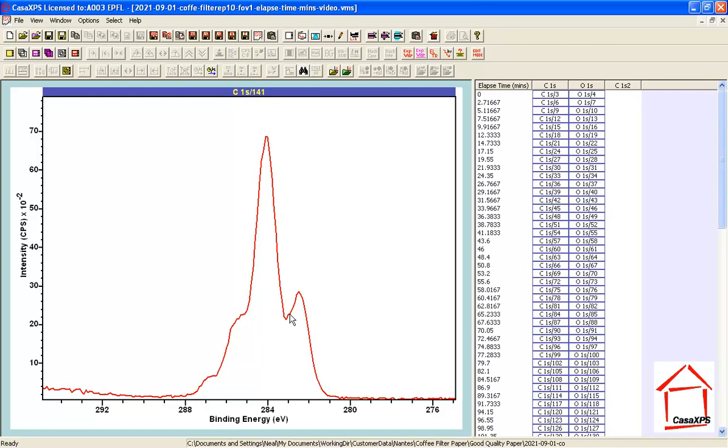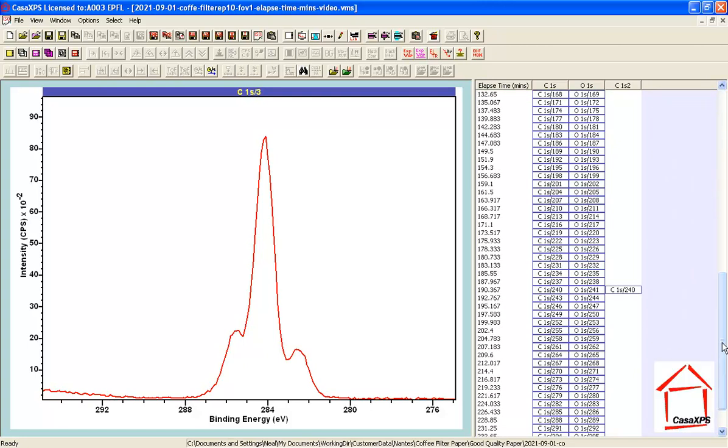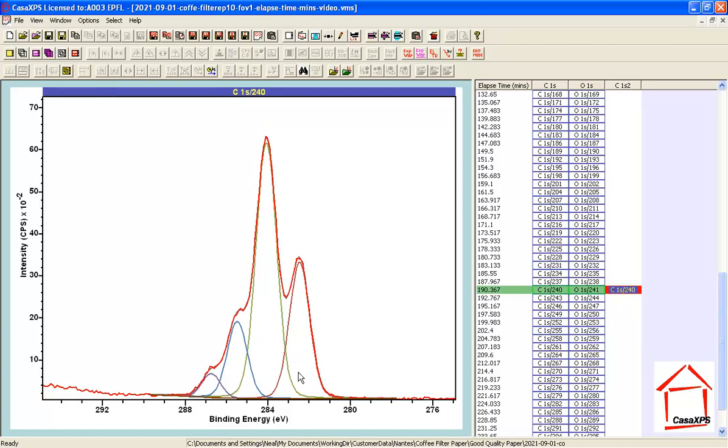Then what we would like to do is be able to fit a spectrum such as this with components that are consistent with other fits throughout the entire data set. So let me illustrate what I mean by an inconsistent peak fit. Here is a peak model. Now, you can argue over whether there are four, five, or more peaks in this peak model, but at least in this instance, four component peaks fit these data, and throughout the entire data set, four component peaks appear to allow fits to data that are consistent with pulse counted data.